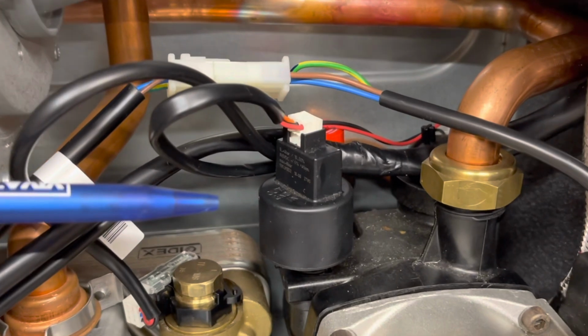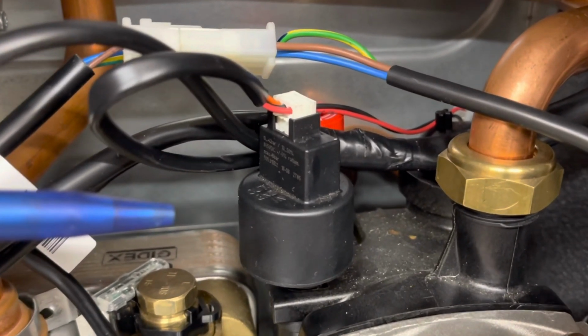First off, this one, the transducer. It's basically an electronic device which converts energy from one form to another. So in our case, we're converting water pressure into an electrical signal. Some people call this a pressure sensor, but it's technically not a sensor, because a sensor will only give an output in the same format. A transducer will actually convert the measurement into an electrical signal.